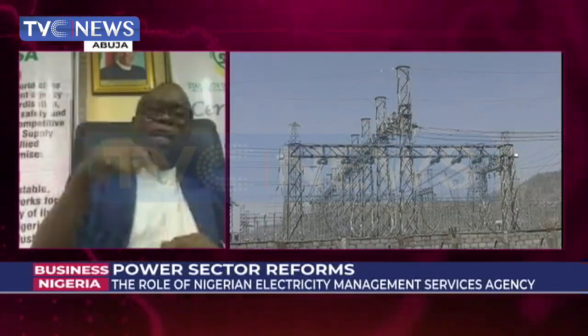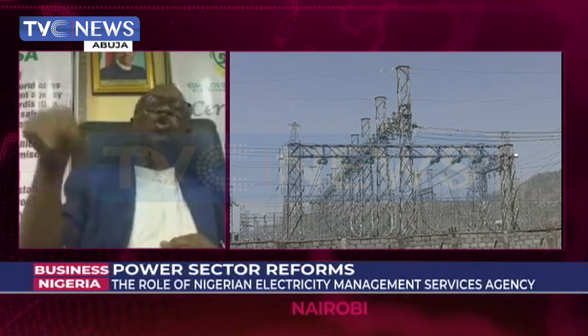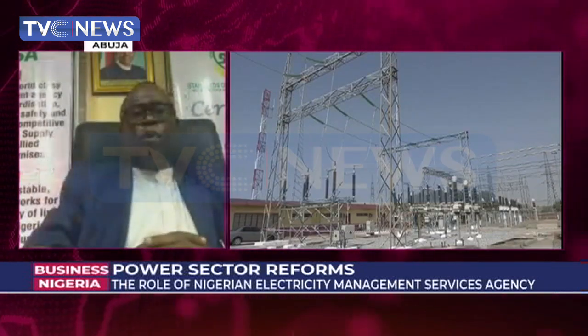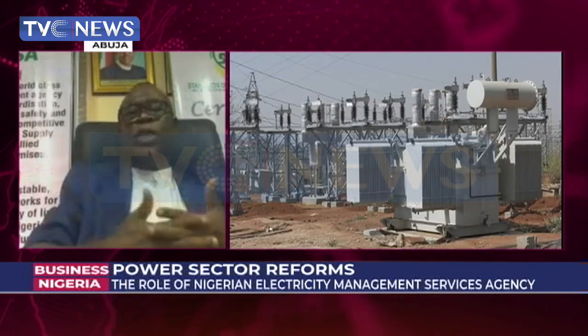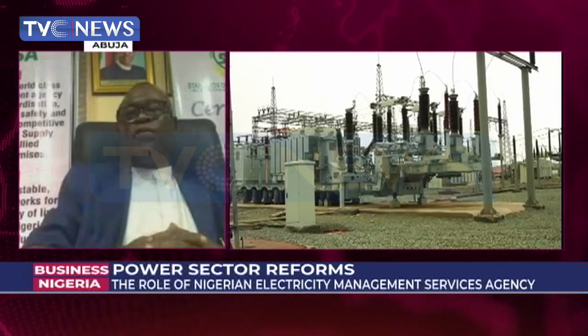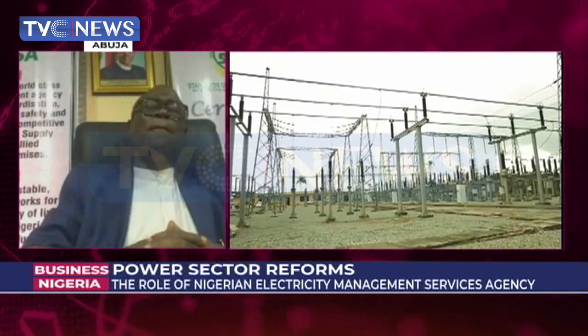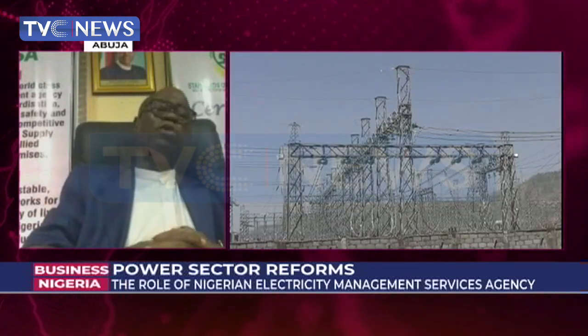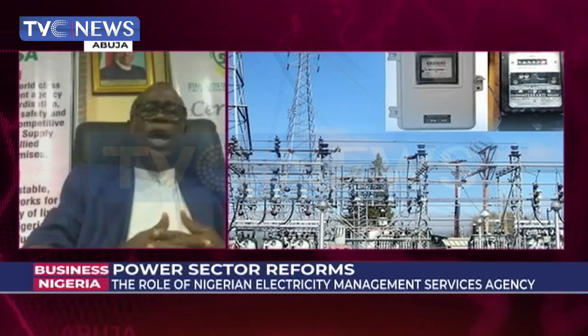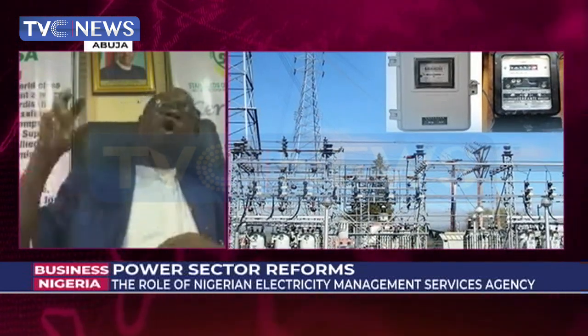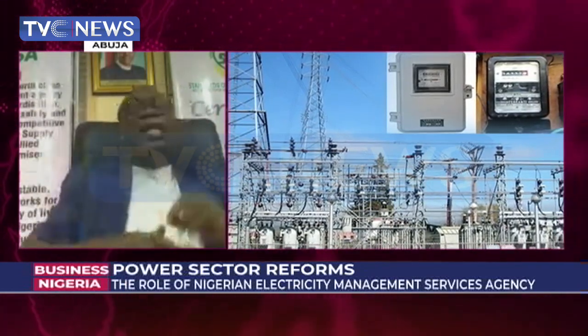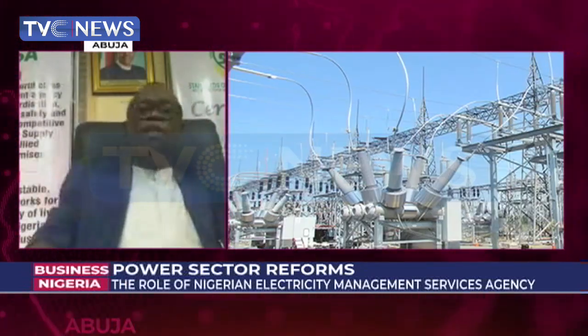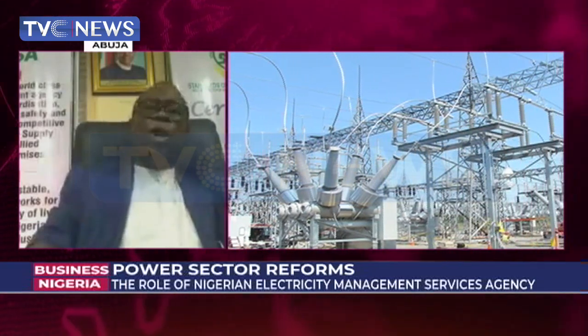The primary distribution is to carry power from transmission station down to what we call injection substation, where the power is knocked down to 11 from 33, and it is 11 that is actually used to feed the generality of the populace in line with the regulation. But what has happened is that in the past, people have tried to use this 33 kV primary feeder line, which is supposed to evacuate power from transmission to general substation, to feed point load. And by this, most of the power will have been completely usurped to the extent that there is no power now getting to 33/11 injection substation, and the larger populace do not have power.